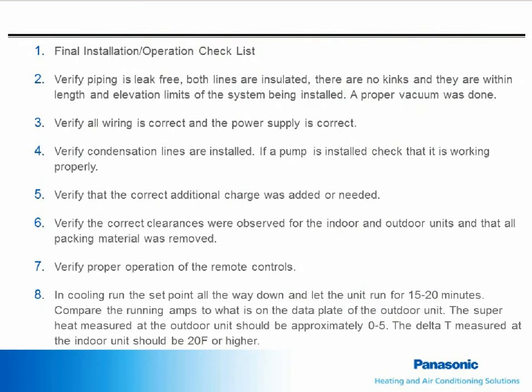Before starting the equipment and completing the job, go over your installation. Verify that the line set was pressure checked and vacuumed, that both lines are separately insulated and there are no kinks in them. Verify the line lengths and elevations are within the limits of the equipment installed. Remember, there should be no dryers or sight glasses in the lines. Verify that the wiring and the voltage is correct. Make sure that both power supply legs are hot. Sometimes lights will come on dimly and the indoor fans will run slowly with just one leg of power.